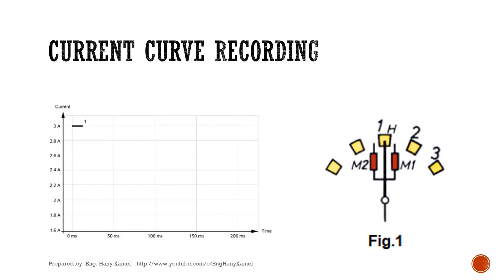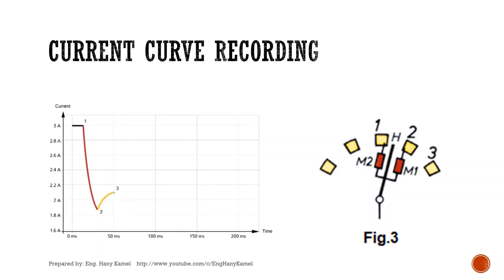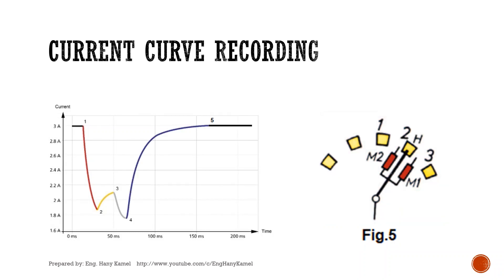For current curve recording: as the tap changer is at tap number 1, the injected DC current is, for example, 3 amperes and stable. When we change to tap number 2, the main moving contact leaves tap 1, and the left transition moving contact with its resistor R2 carries the current — so current drops. The right transition moving contact then reaches tap 2 while the left transition contact is still on tap 1, giving current paths through R1 and R2, so current increases. The left transition contact then leaves tap 1, so current flows through R1 only and drops again. Finally, the main moving contact reaches tap 2 and current returns to 3 amperes.